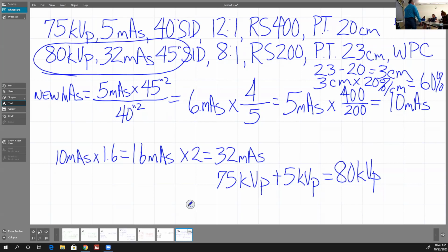Right there. I don't know if this is a stupid question. No, but ask away. So what do you mean by fixed kVp then, if you just change the kVp? That is not a stupid question. That's a good question. It comes up every year. Remember, when we talk about fixed or variable kVp, that is only for a change in tissue thickness. In other words, even with a fixed kVp system, I could say, hey, I want a lower energy beam, and I could change my kVp and compensate with mass. Does that make sense? Yeah. So it's only for tissue thickness change.